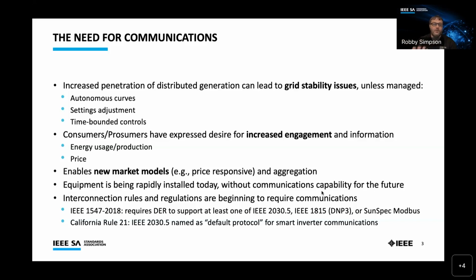One thing to consider is that this equipment is being rapidly installed today. Every day I hear new predictions about the installation of renewables that are quite exciting and always seem to revise themselves to be more aggressive. But a lot of this is being installed without communications capability. The concern is that once they're deployed without communications, it's going to be very hard to communicate with them in the future, or to adjust those settings and deal with grid stability issues that arise.